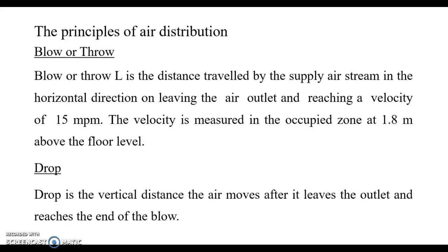The principles of air distribution. The first one is the blow or throw. Blow or throw means the distance traveled by the air stream in the horizontal direction on leaving the air outlet and reaching the velocity of 15 meter per minute.